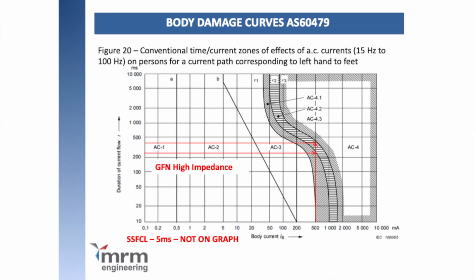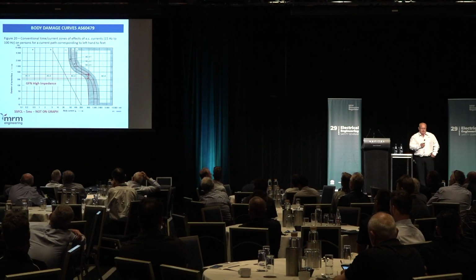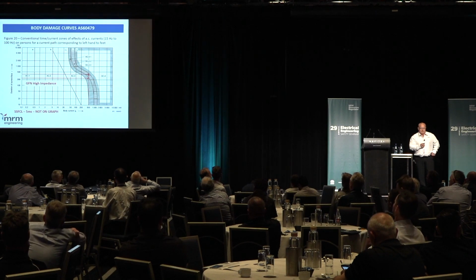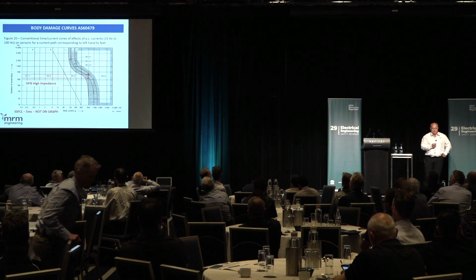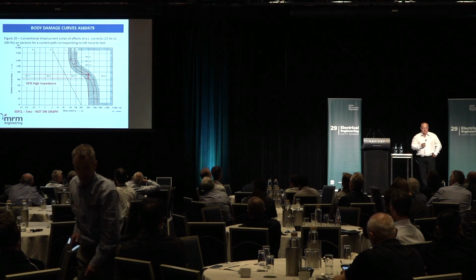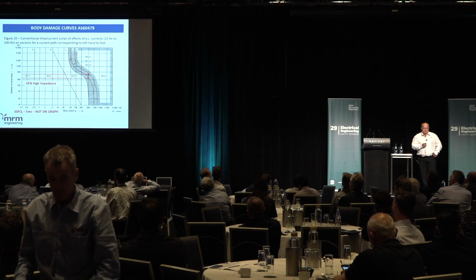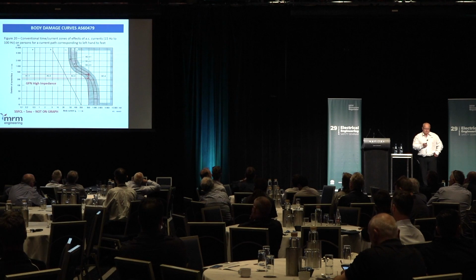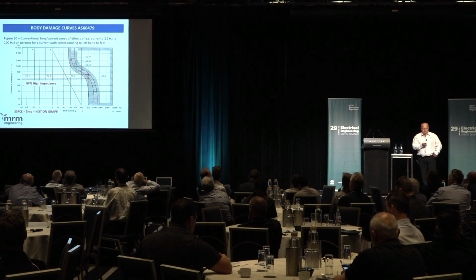So this is out of AS60479. This is your body impedance curve. So you can see that for a ground fault neutralizer on high impedance, it's not going to offer a lot of protection for people, but the solid state one, it doesn't even appear on the graph because it's that fast.